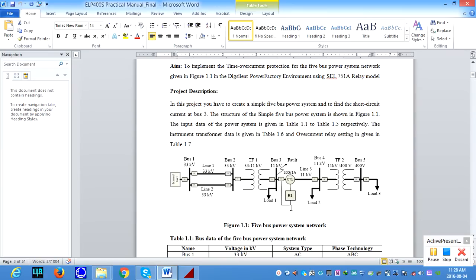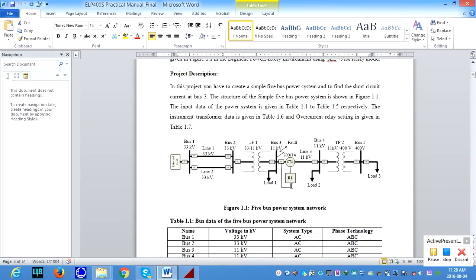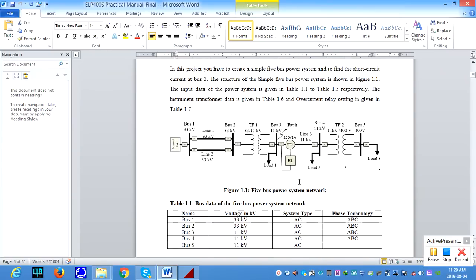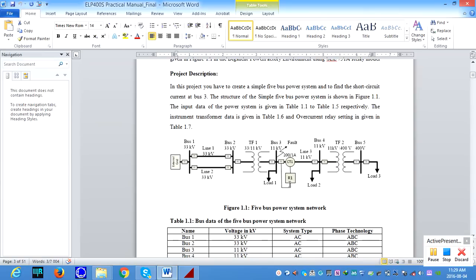The aim of this experiment, especially for the protection setting aspect, is to use the SEL751 feeder protection relay at bus 3 as shown in this figure. It's just an overcurrent relay, so we need a CT which is able to measure the current flowing through this line, and it can configure the relay settings. If, for instance, you assume there is a fault at bus 3, the CT will sense the current and feed its output to the relay, and if there is a fault on the network, the relay can issue a trip signal to the breaker and the breaker can open.